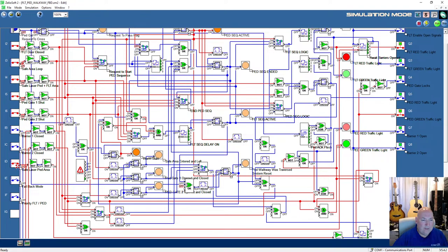Don't go through, it'll be fine. If I break the area, it'll cancel off the timer. And it'll start counting again as soon as I leave the zone. Right, okay. So that's a little bit better. Now, I need a 3 second delay so this cannot switch straight away. Needs an on and an off delay, I think. Every time it switches, because as soon as the barriers switch off, it takes 3 seconds for it to close. Yeah, but they close straight away, and then as soon as they switch on, when it switches on, it goes off straight away, or half a second.